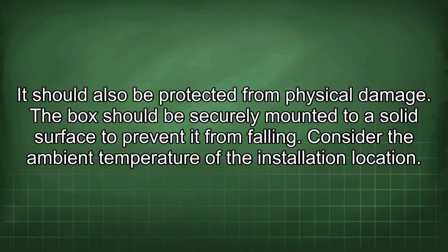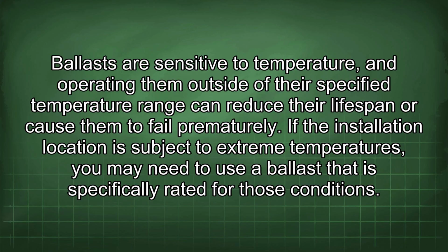Consider the ambient temperature of the installation location. Ballasts are sensitive to temperature, and operating them outside of the specified temperature range can reduce their lifespan or cause them to fail prematurely. If the installation location is subject to extreme temperatures, you may need to use a ballast that is specifically rated for those conditions.